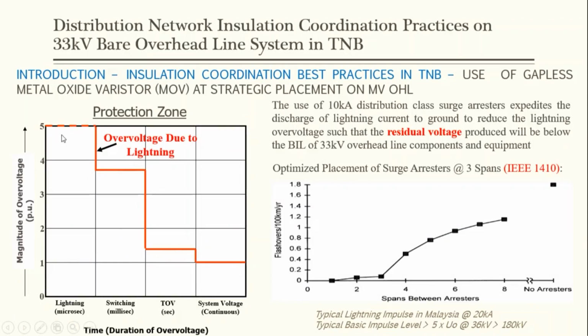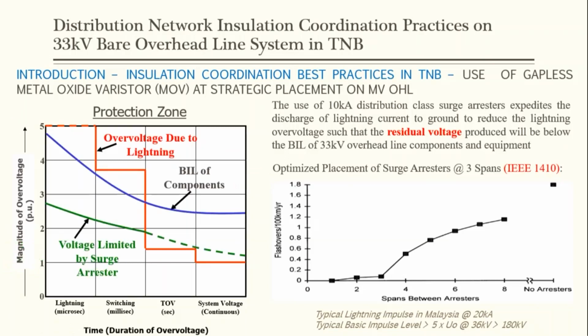Lightning overvoltage can be more than 5 U0. For example, if we take a simple calculation, this can be up to 180 kV, but that is already more than the BIL of components, because for 33 kV, the BIL of our components will be about 170 kV. So the lightning overvoltage will be more than the BIL of the component. When we install the surge arrestor, it will limit the lightning overvoltage below the BIL of the components, and it will give a protective margin of about 25% to 30%.